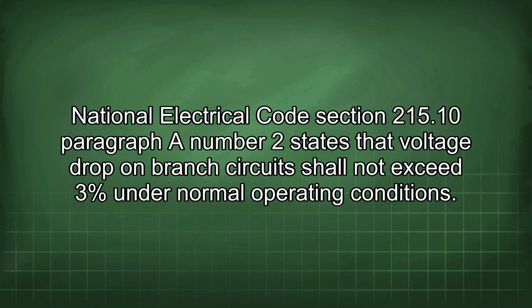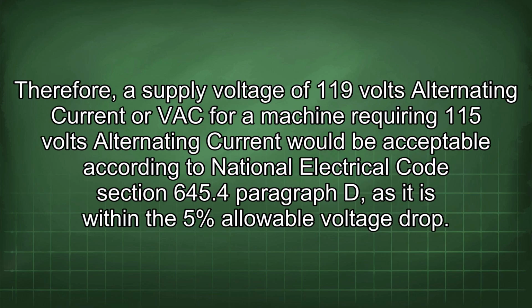National Electrical Code Section 215.10 paragraph A number 2 states that voltage drop on branch circuits shall not exceed 3% under normal operating conditions. Therefore, a supply voltage of 119 volts alternating current or VAC for a machine requiring 115 volts alternating current would be acceptable according to National Electrical Code Section 645.4 paragraph D, as it is within the 5% allowable voltage drop.